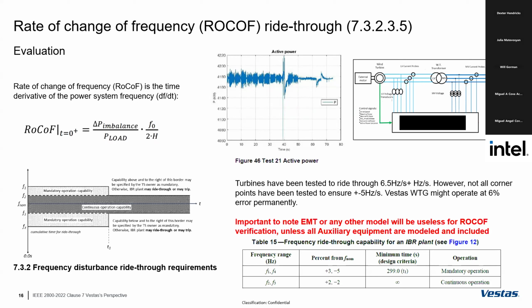I will give you a very simple example. When we evaluate ROCOF in a lab containing actual hardware in the loop, we can pass huge amounts of ROCOF in the 2-digit level. But when you actually evaluate the same ROCOF in the field, you will realize the turbines will trip. And they will trip, and I think someone mentioned it before me, because some of the auxiliary services need to be considered. So those auxiliary services might trip due to ROCOF, but your converter will not.